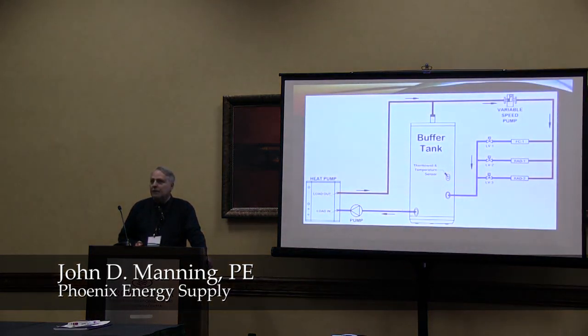Every diagram you'll find in every book indicates: we go to the heat pump, come back, put it in the buffer tank, go out to the load, come back, mixing in the buffer tank. And this is the basis for our initial base case modeling — it represents the best case documented in any literature. The other variations would show even greater results than this because at least in one variation we were coming out of the top of the tank to go to the load. But there's no stratification in these tanks — they're turned over so quickly it's a big mixing pot.